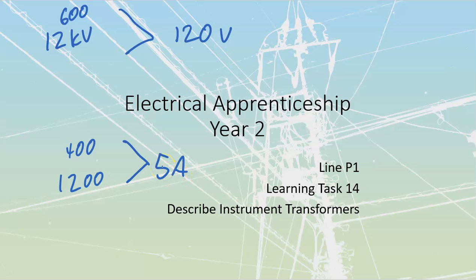Now they're not cutting off the customer, it's not like they're saying you don't get more than 5 amps. Instead, through instrument transformers they create a sliding scale, so as the customer varies from 0 to 1200 amps, in the case of a 1200 amp service, that's reflected as varying from 0 to 5 amps, directly proportional, and then they just do the math.